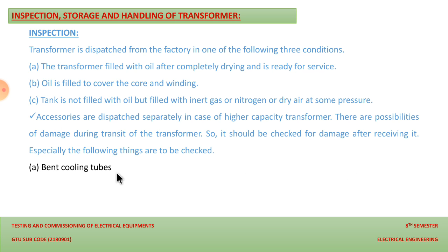And the second is damaged protruding fittings. Some of the fittings will get loosened during the transit. So you have to check the fittings and the damage of the fittings that we have provided on the transformer.